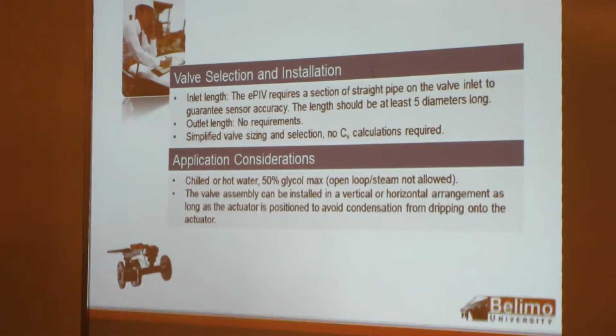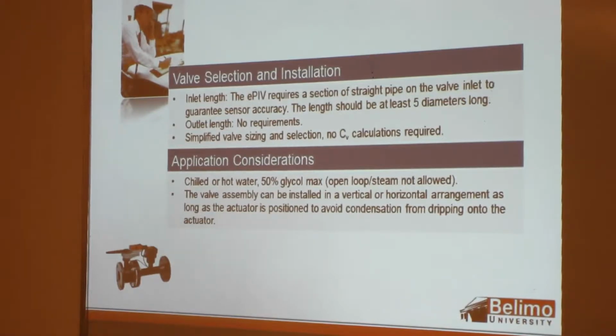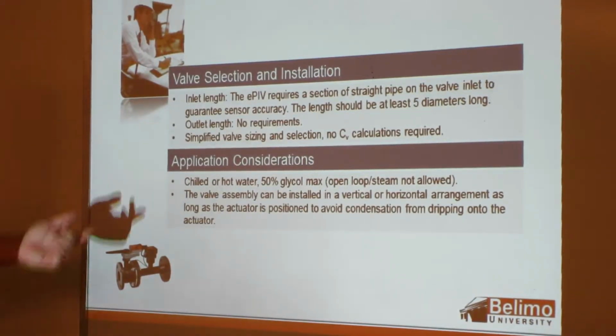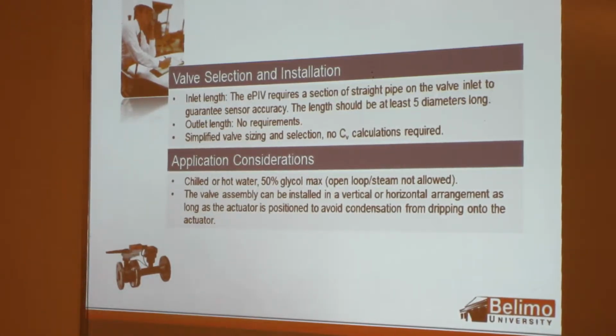Selection installation information. Inlet length. This is one thing that's a little different than what we say, but it's really part of best piping practices for all valves. EPIV requires a section of straight pipe on the valve inlet, 5 pipe diameters. We don't require anything on the outlet side. Simplified valve sizing, as I said on the PICCV, you're sizing up these valves based on your GPM as well.